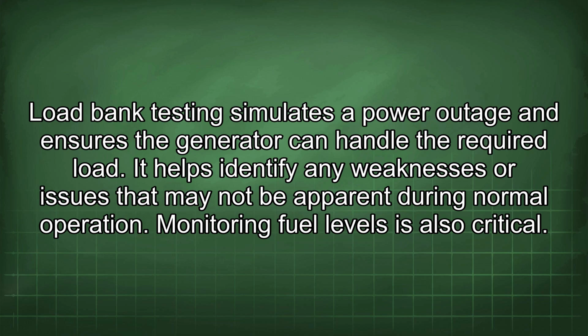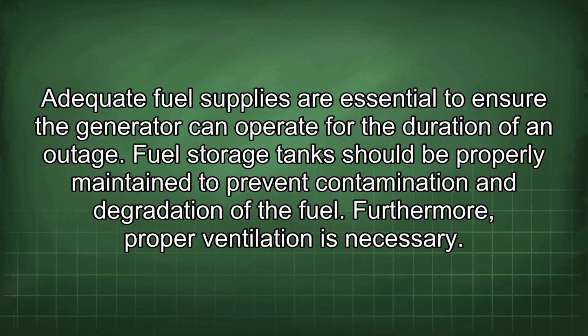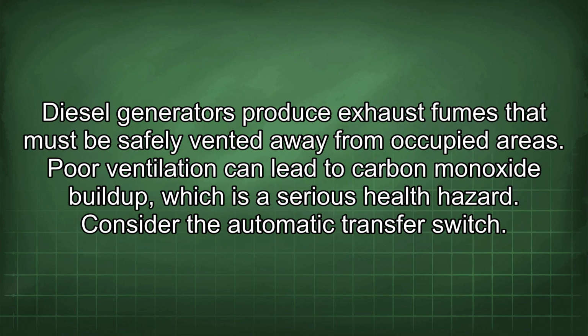Monitoring fuel levels is also critical. Adequate fuel supplies are essential to ensure the generator can operate for the duration of an outage. Fuel storage tanks should be properly maintained to prevent contamination and degradation of the fuel. Furthermore, proper ventilation is necessary. Diesel generators produce exhaust fumes that must be safely vented away from occupied areas. Poor ventilation can lead to carbon monoxide buildup, which is a serious health hazard.